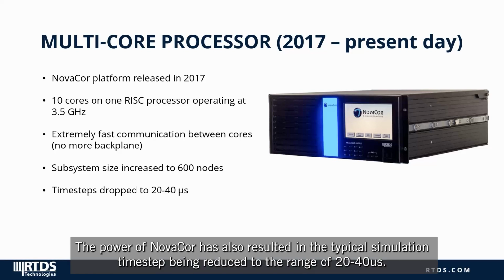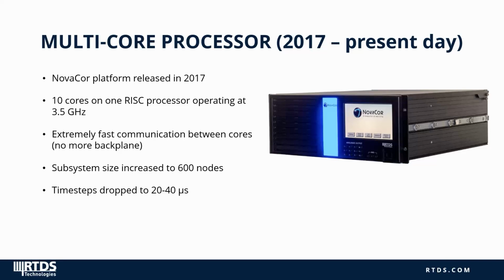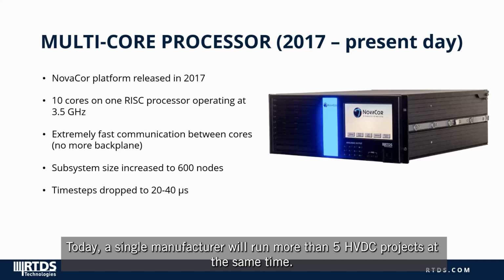The power of NovaCor has also resulted in the typical simulation time step being reduced to the range of 20 to 40 microseconds. Today, a single manufacturer will run more than 5 HVDC projects at the same time.